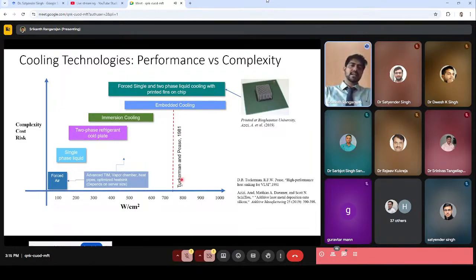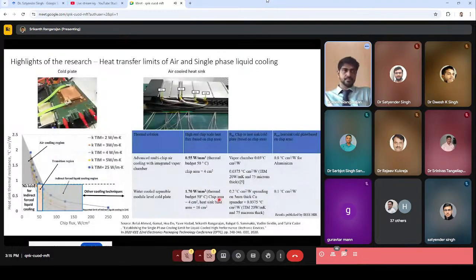The Tuckerman and Pease paper, published in 1981, showed that embedding the cooling solution directly on the backside of the chip using single-phase microchannel cooling can remove heat up to 790 watts per centimeter square. But today we're talking about more than 1 kilowatt per centimeter square, so we have to go for more aggressive cooling solutions.